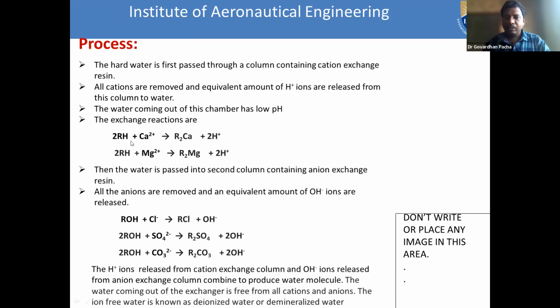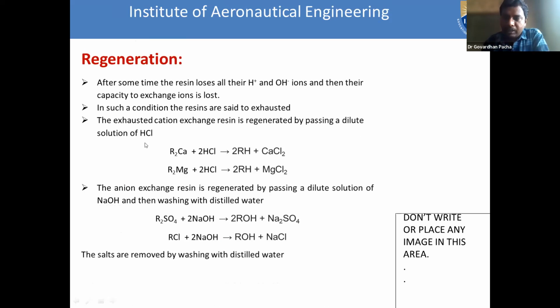In the previous equations, we see the cation exchanger filled with the cationic hardness and the anion exchanger filled with the anionic hardness. These are the products. Now, by taking these products, the regeneration takes place. Initially we regenerate the cation exchanger. The cation exchanger is always regenerated with dilute hydrochloric acid, whereas the anion exchanger is always regenerated with dilute sodium hydroxide.